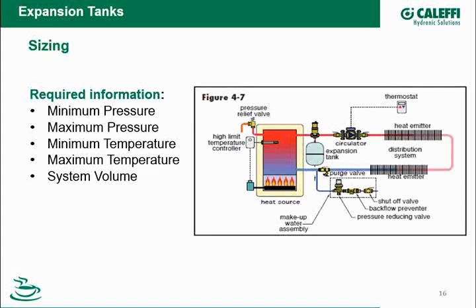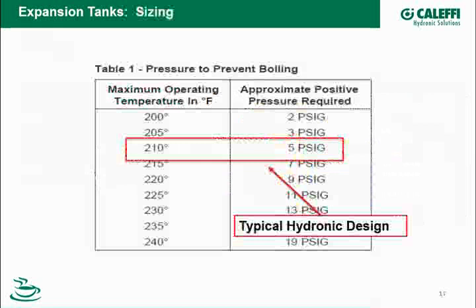Now, for the minimum pressure, I have to start somewhere. This is a table that talks about positive pressure to prevent boiling. We also need positive pressure on the top of the system for air vents to be positive acting. Typical hydronic design normally looks at 5 pounds of positive pressure at the top of the system. With a safety factor, I can get up to 210 degrees and not worry about the water boiling. Additionally, for air vents, 5 psi is going to give that air vent enough positive pressure that it will act properly and won't weep.